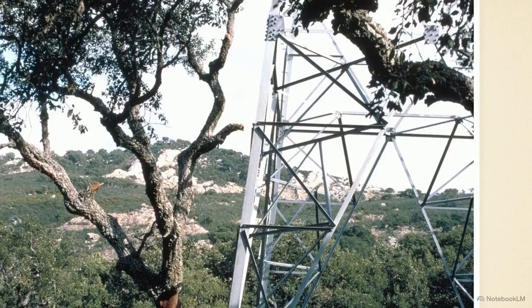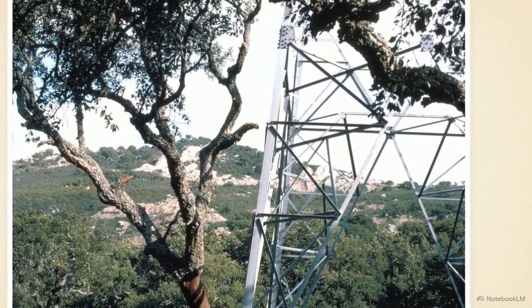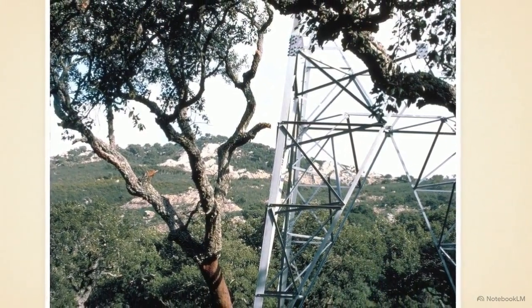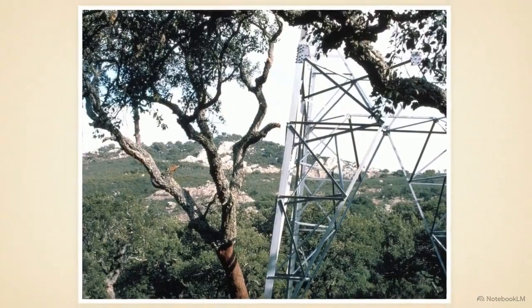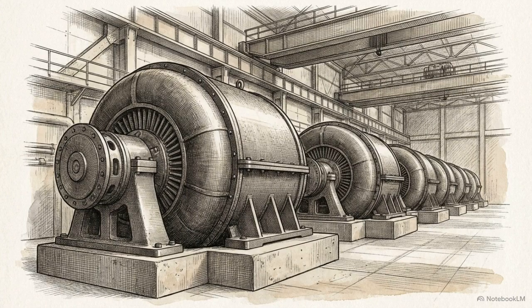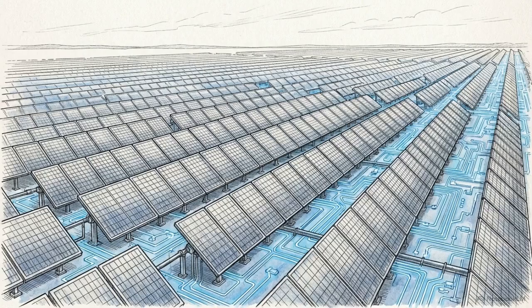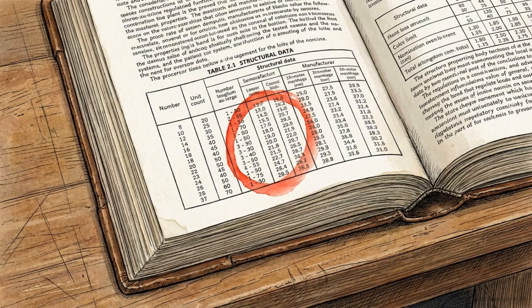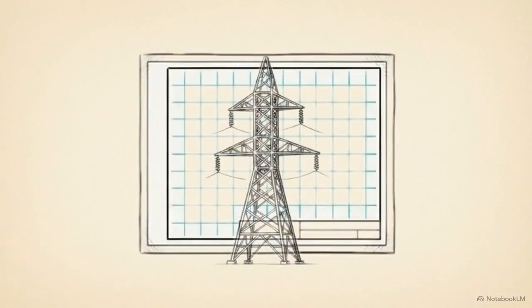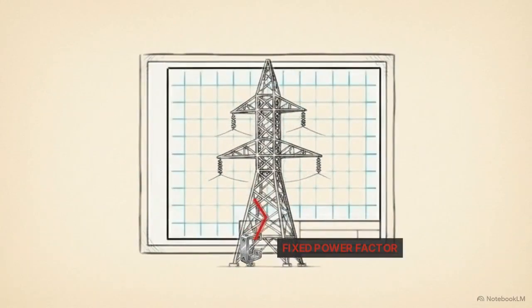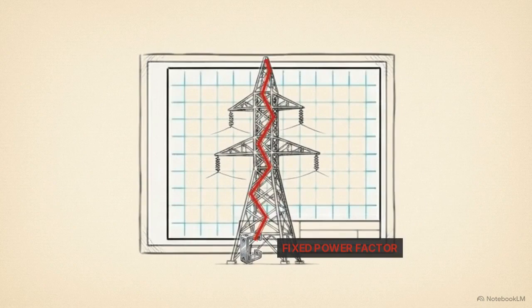The 2025 Iberian blackout carries distinct implications for the global energy transition. The old paradigm relied heavily on the physical inertia of massive spinning turbines to self-regulate. The modern grid relies on complex networks of inverter-based resources. This blackout demonstrates that relying on static regulatory metrics, such as forcing renewables to operate on fixed power factors, is a fatal flaw in modern grid architecture.